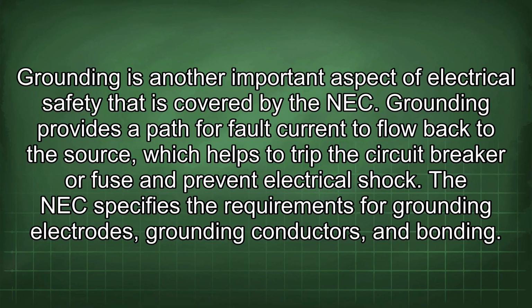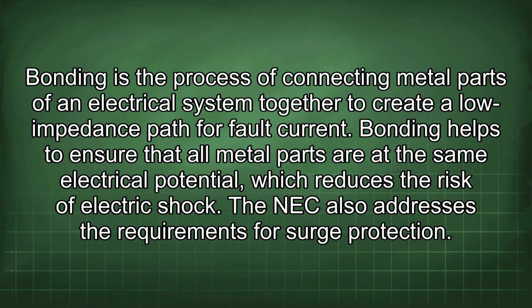Grounding is another important aspect of electrical safety that is covered by the NEC. Grounding provides a path for fault current to flow back to the source, which helps to trip the circuit breaker or fuse and prevent electrical shock. The NEC specifies the requirements for grounding electrodes, grounding conductors, and bonding. Bonding is the process of connecting metal parts of an electrical system together to create a low impedance path for fault current. Bonding helps to ensure that all metal parts are at the same electrical potential, which reduces the risk of electric shock.